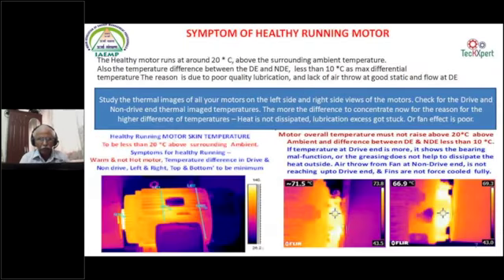Coming to the symptoms of healthy motors. You can find in some of these thermal images, we have been using thermal images for almost 6 to 8 years and above. Some of the readings are taken from all of our energy audit work. I went back through and studied this, and in many of the motors we found that between the driven and non-driven end, the temperature difference is almost 30 to 35 degrees. The difference is more. You can see the image, bottom left.